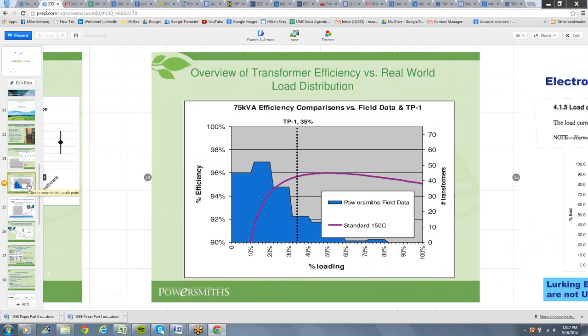Well, it's important because transformer efficiency is a curve, and as you can see, it peaks in efficiency at 30, 40, 50% load, but as you lighten up, going to 30, 20, 10, the efficiency of the transformer noses off. It just falls off a cliff. And guess what? That's exactly where the loading is. So you have the impression on one hand, because there's this minimum legal efficiency, that you're going to get that efficiency. But in fact, because the loading's not there, you're not anywhere near that kind of efficiency, right? And losses are the flip side of efficiency. So you can see, a 96% efficient transformer means 4% losses. Down at 10% load, we're at a 90% efficient transformer, meaning 10% losses. So we've gone from 4% to 10%. So a pretty big difference in terms of where we think the transformer is operating. So loading, as you can see, is very important.